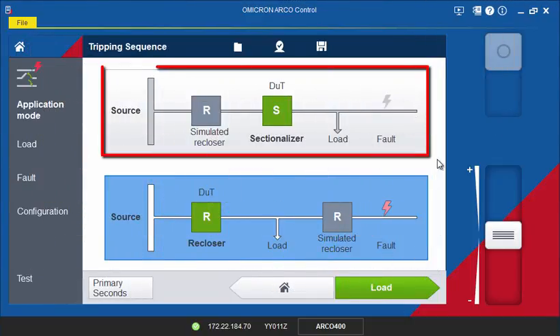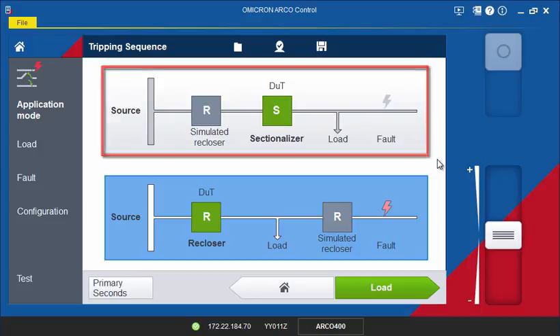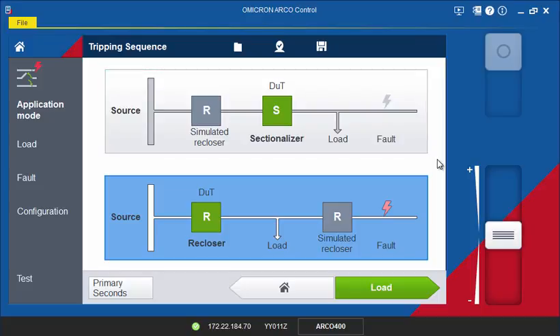For testing sectionalizer controls, use the sectionalizer application mode. This test setup is similar to the recloser mode, but in this mode an upstream recloser is simulated.